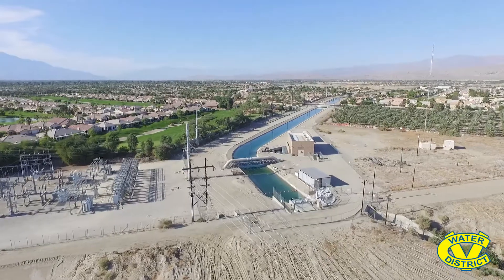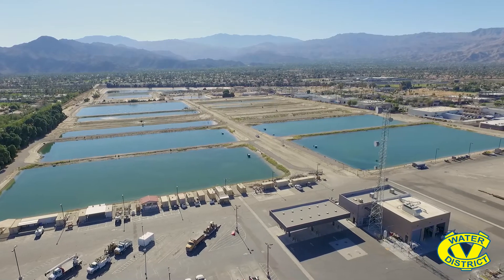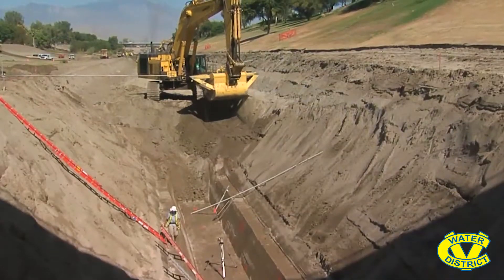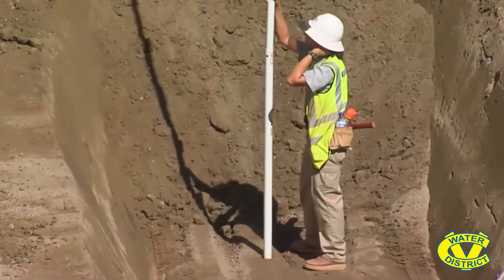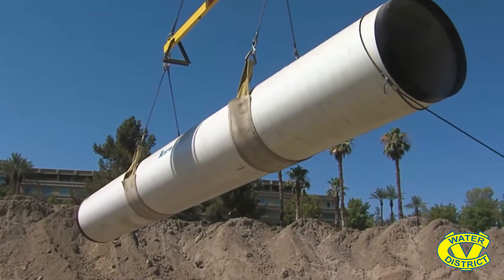This Mid-Valley Pump Station is towards the end at milepost 115.5 of the 123-mile Coachella Canal and it delivers water to WRP 10 in Palm Desert, which is seven miles away. The pipeline that delivers the water is 54 inches in size and it's about seven miles long. The top of the pipe is 20 feet underground because it's placed within our Coachella Valley Stormwater Channel and our Whitewater River Channel, where all the stormwater flows travel through, and we don't want the pipe scoured or exposed.